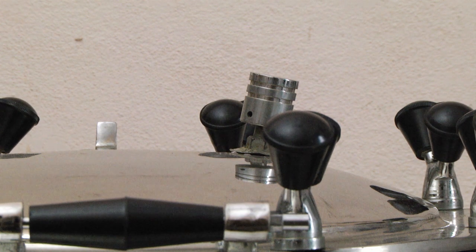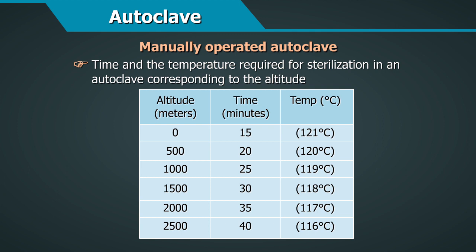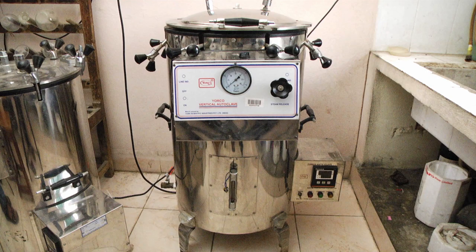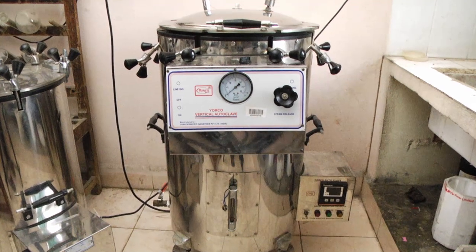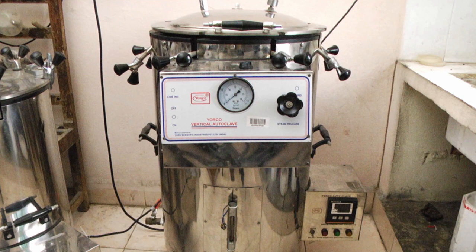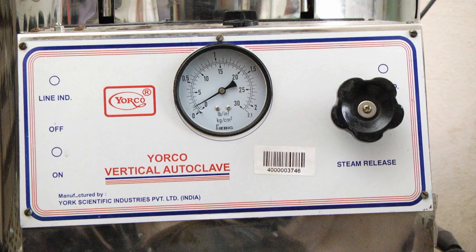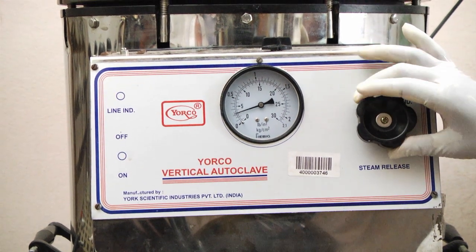The heat should be sufficient to maintain the required pressure for the duration of the sterilizing time. Depending on altitude, set the timer accordingly — a chart gives the time and temperature required for sterilization corresponding to altitude. At the end of the sterilizing time, turn off the heat and allow the autoclave to cool naturally, which may take several hours, particularly for culture media. When the thermometer reads below 80 degrees centigrade and the pressure gauge registers zero, slowly open the draw-off cock to vent the autoclave.